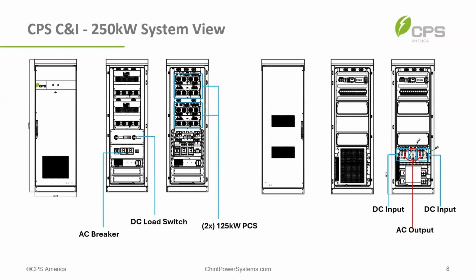This setup right here is the 250 setup, so you'd have this PCS and then a battery cabinet on one side, battery cabinet on the other side, or however you want to configure it. We could add the exact same thing next to it, parallel it all together, and run that to a single EMS doing the high level control of everything. We can do that up to 8 of them together whenever we're grid tied.